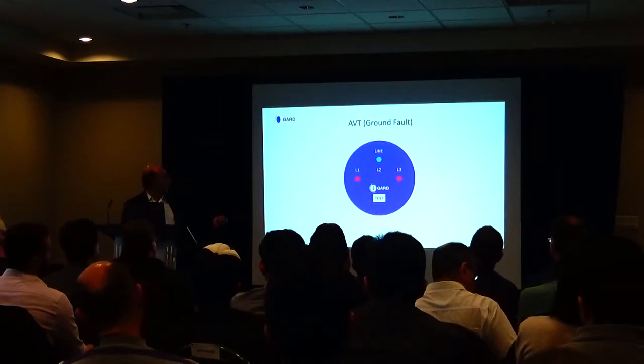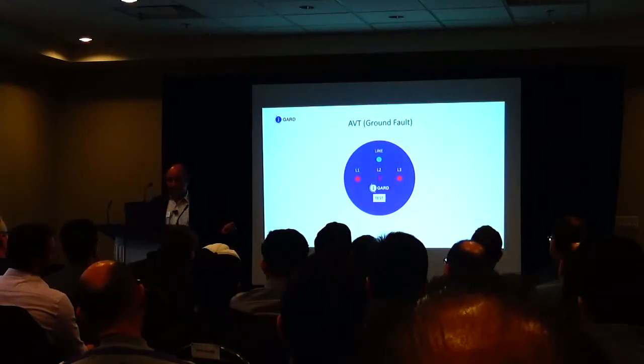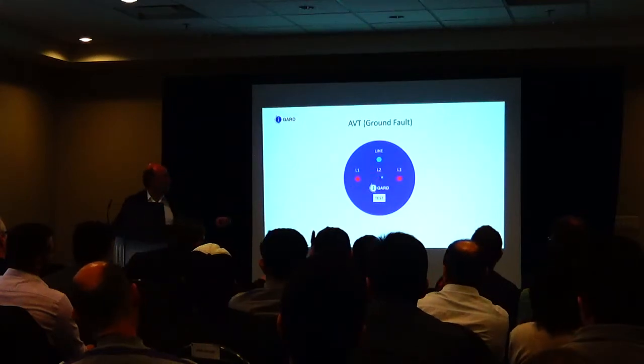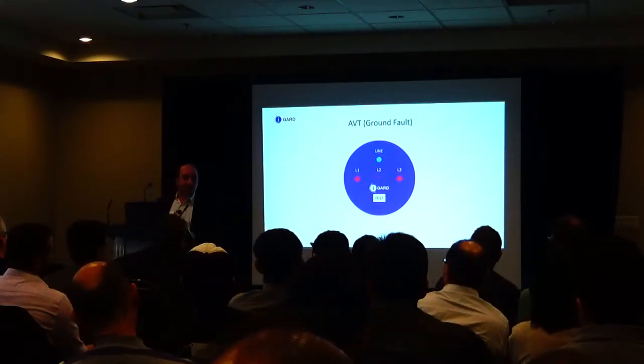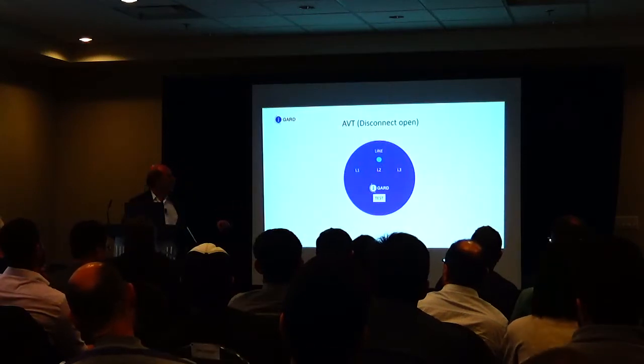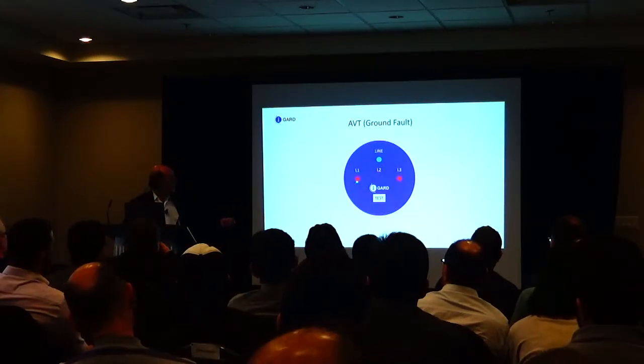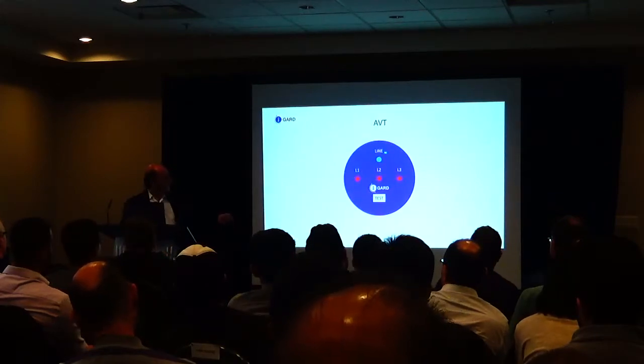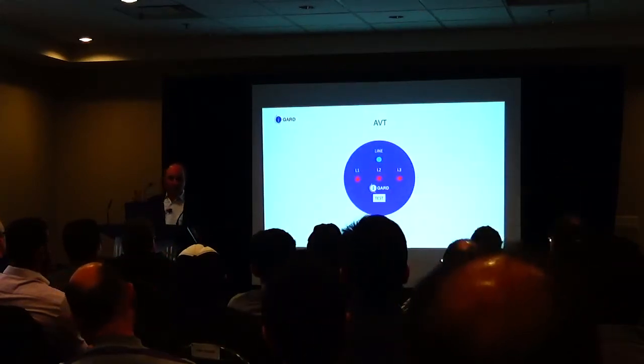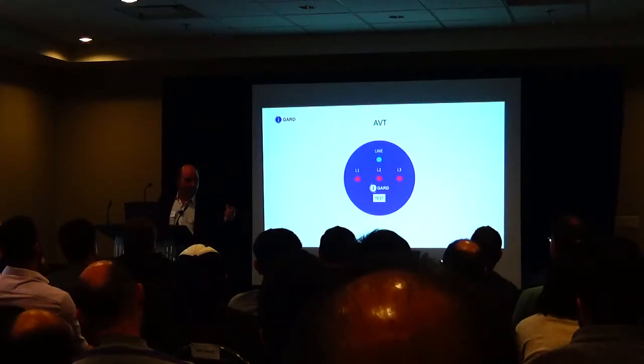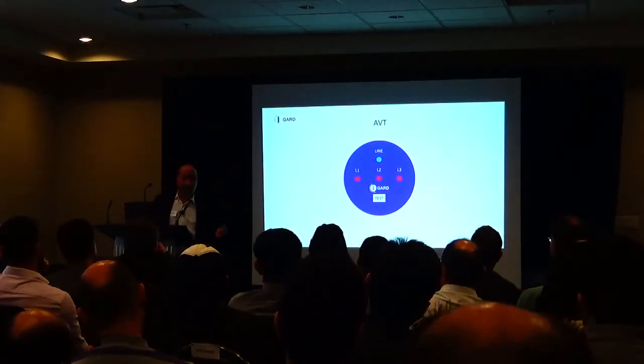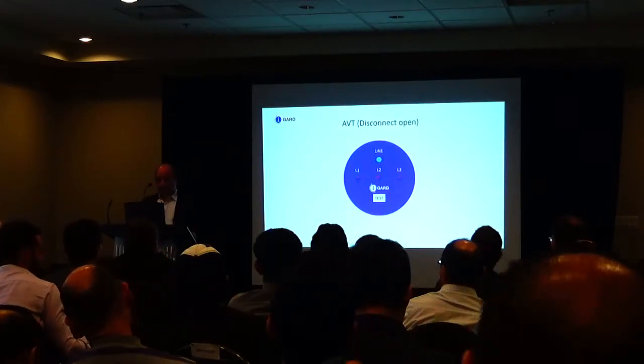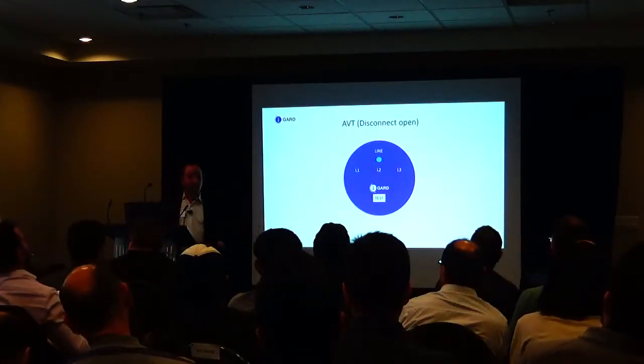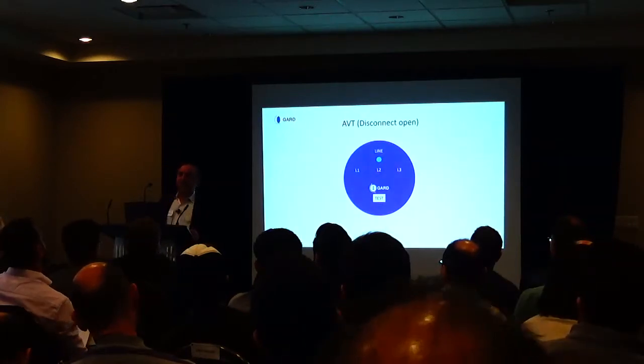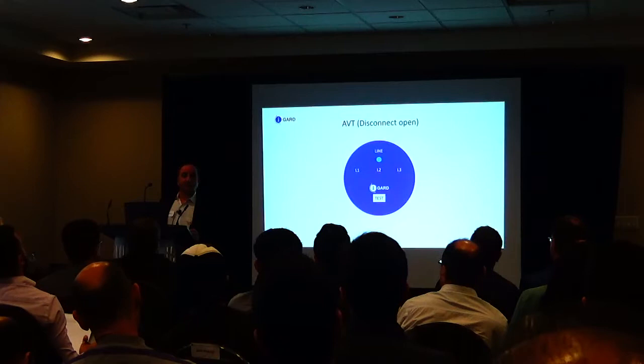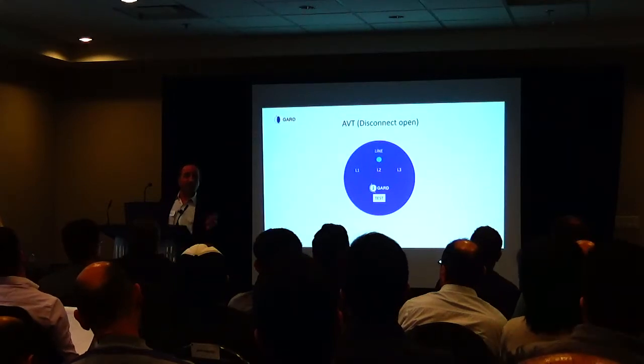So when you have a ground fault, it also determines that. You have a flashing red light that tells you that you have a fault on a particular phase. When the disconnect is closed, if you notice, I have three red lights indicating that the line side is on and three load side lights are on. So I measure L1 to ground, L2 to ground, L3 to ground. If the disconnect is open, those three lights go off. Can we say the system is de-energized? Just because the voltage indication is off, right?